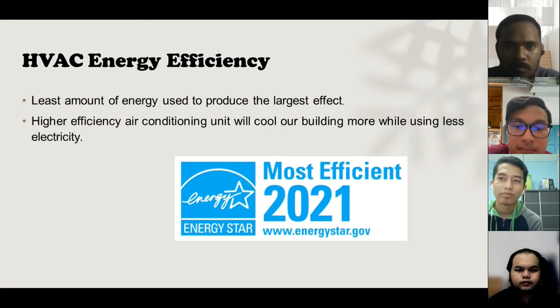There are two types of efficiency. First, energy efficiency ratio, EER. It is the ratio of cooling capacity in BTU per hour divided by the power input. So the higher the EER rating, the more efficient the air conditioner. The second one is seasonal energy efficiency ratio, SEER. It is the ratio of cooling output of an air conditioner over a typical cooling season divided by energy use. So it is the average efficiency of the air conditioning for the whole season.